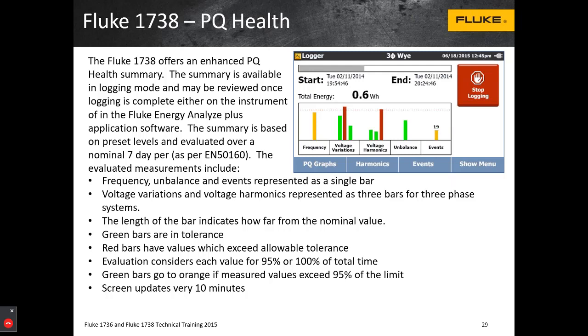So again, this is one of the things built into the Fluke 1738 — the ability to compare data against a standard of measurement. This has impacts on harmonics as well as event measurements, like dips, swells, sags, and also unbalance, as well as frequency changes. So this is just another powerful feature that the 1738 incorporates.